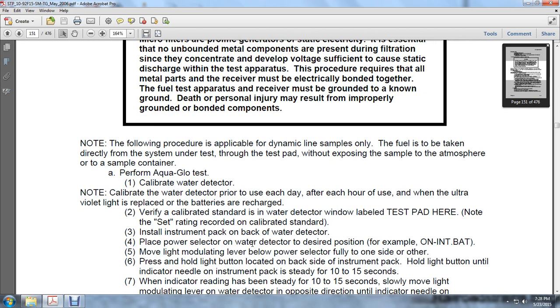After each hour of use, when the ultraviolet light is replaced and batteries are recharged, verify the calibrated standard is in the water detector window labeled test pad. Note the set rating recorded on the calibrated standard. Install the instrument pack on the back of the water detector. Place the power selector on the water detector in the desired position, for example, on battery.